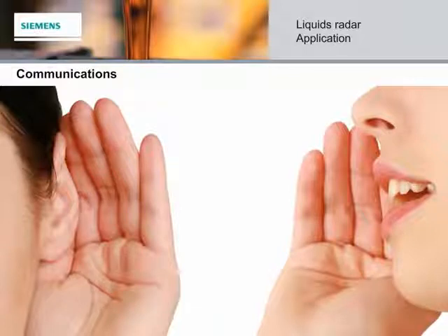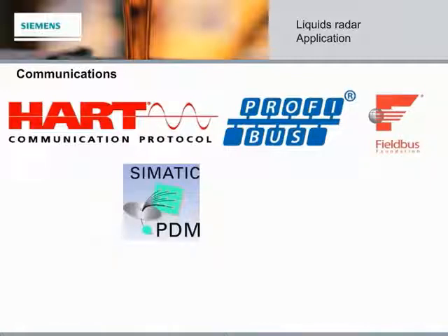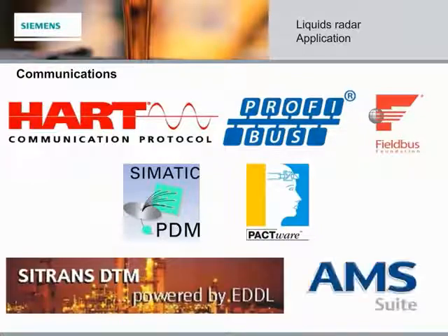Our LIQUIDS Radar family has a variety of communications options. In addition to the standard 4-20 milliamp, HART, Profibus, and Fieldbus Foundation are available. Remote programming can be performed with SIMATIC PDM and FDT tools such as PACTWARE via SITRANS DTM. AMS is also supported. This offers full and user-friendly information exchange between you and your system.